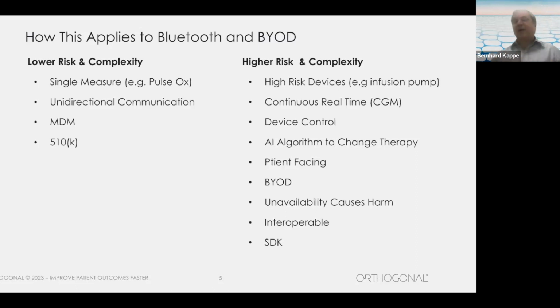On the other end of the spectrum, if what you're doing is connecting to a high risk device, so CGM, infusion pump, pacemaker, all of these types of things, that's a much higher bar. If you're trying to get continuous real-time data in the background, again, for something like that, a higher bar. You're actually controlling those devices and controlling therapy using your smartphone. Okay, again, the bar gets higher. You have an AI algorithm in the smartphone or on the cloud that uses data from the smartphone and from the device to actually then automatically change the therapy. Again, a higher bar.